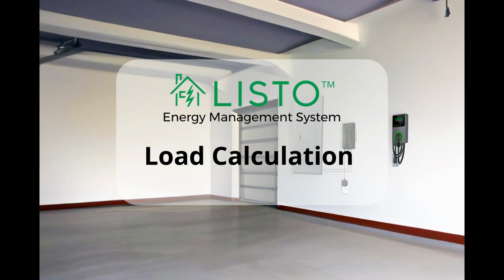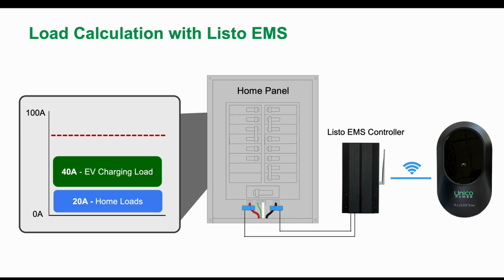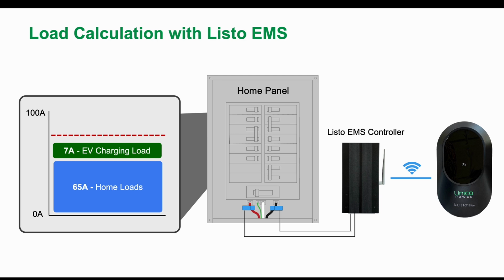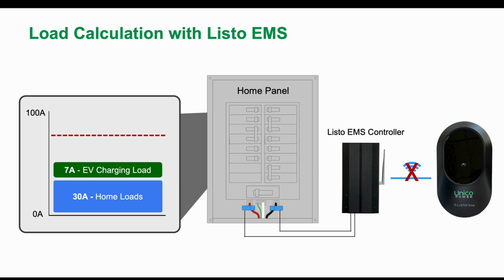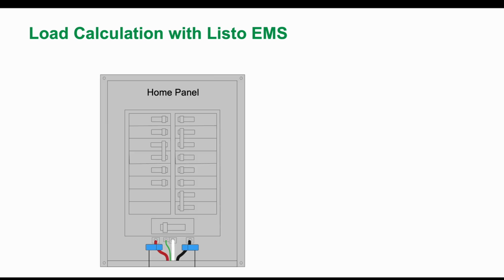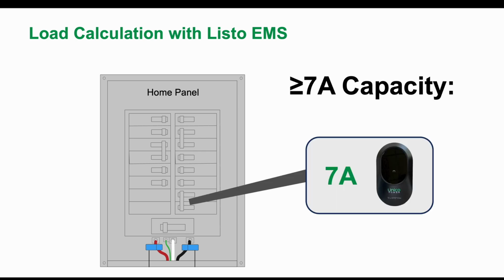How does the Listo EMS affect the load calculation? EV owners require little or no capacity on their panel to enjoy fast Level 2 charging. With Listo EMS, the EV charging load is controlled down to its lowest output when demand in the panel is high, or communication is lost between the EMS controller and the EVSE. This low limit, known as the fail-safe limit, is generally set to 7 amps.